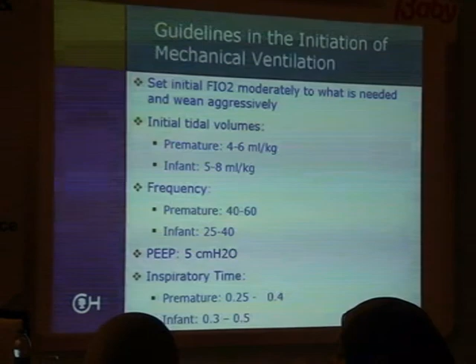And then for our inspiratory times, for premature infants, it's going to be 0.25 or out to 0.4 seconds for each individual breath. And again, really watching our waveforms to see if we're starting to see that peak at the end of inspiration where the patient is wanting to actively exhale, and shortening that inspiratory time a little bit. It's one of those settings that oftentimes people kind of set and then forget about. They think, well, you're 25 weeks, therefore you're going to need this inspiratory time, and now you're 2 months old and you still have the same inspiratory time.